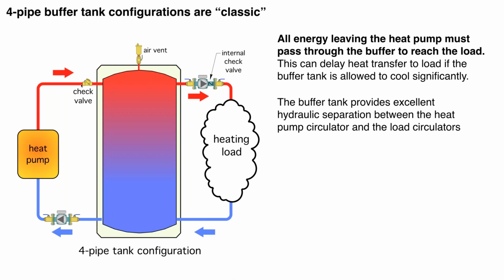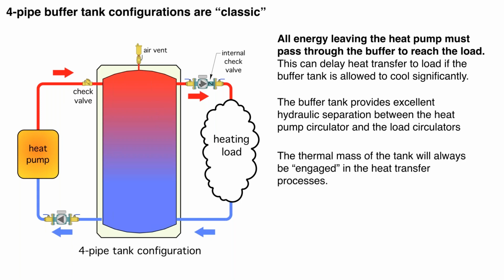That's the ideal scenario. And piping a buffer tank like this is one way to achieve good hydraulic separation between the heat pump circulator and the circulator for the distribution system. Again, all the thermal mass of the tank is fully engaged here, okay? In many cases, that's a beneficial effect. In some cases, when the tank is cold and we're trying to get energy directly to the load, it tends to work against us.